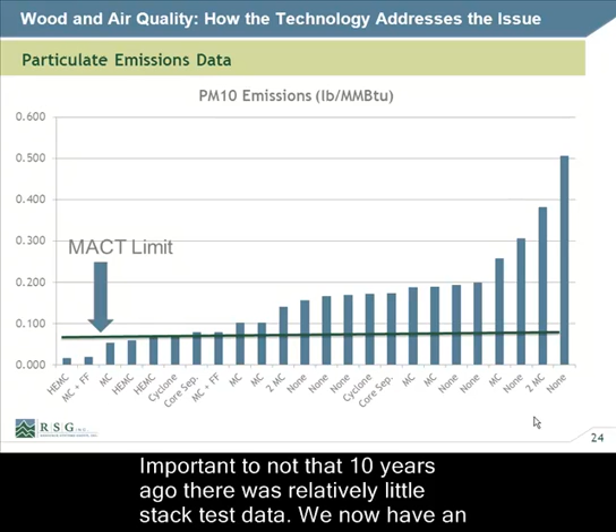What this really shows is that if you want to install a new large boiler, more likely than not you're going to need some type of advanced emission control technology. In some cases you would not need them — there are some systems that can be below 0.07 with just a cyclone.